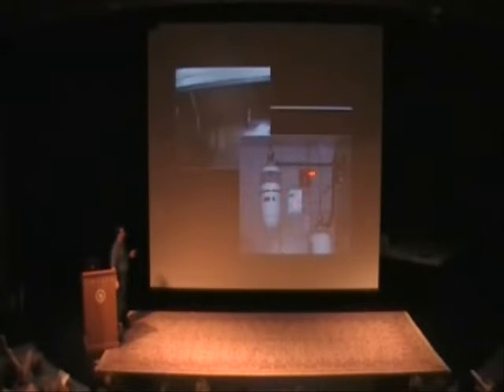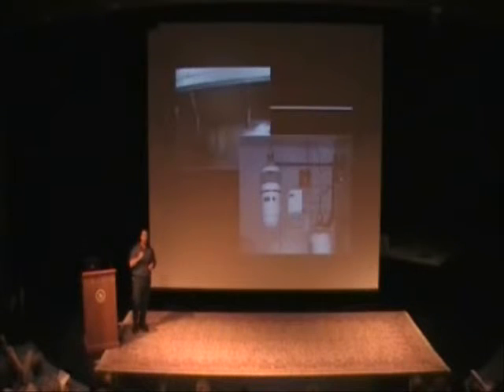This is your system. That alarm right there goes to this system. These here are plastic caps for your spray nozzles in your hood. If you see them and they're just dangling, they need to be stuck back on there. What happens is that grease vapor gets in there. There's a little nozzle inside there. The grease will plug that up and it will not spray. The grease fire, kitchen fire will get out of control and your business will be shut down longer than you want it to be.